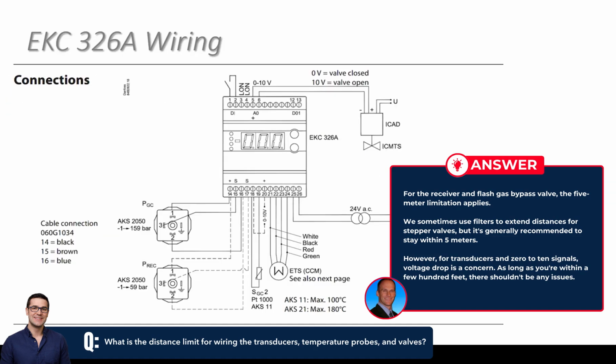And then when you get into the other items here, the transducers, the 0 to 10, you're worried about maybe some voltage drop. As long as you're within a few hundred feet, we don't see issues, and that's normally more than enough distance to cover what we would see for the wiring between those 2 devices.